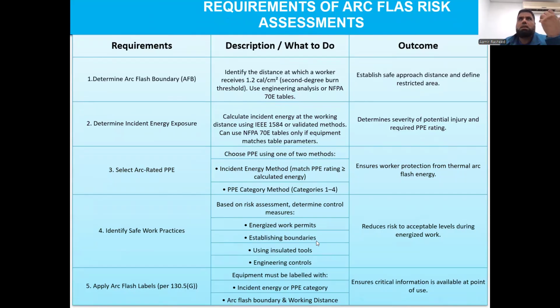So the next is requirements of arc flash risk assessment. When we are talking about the arc flash risk assessment, once the risk is evaluated, it requires specific outputs to determine your arc flash boundaries, what the incident energy exposure is, the severity of potential injury, and the PPE required there. Selection of the right arc rated PPEs is based on the incident energy method. And what the PPE category method is, we are going to discuss in the next one.